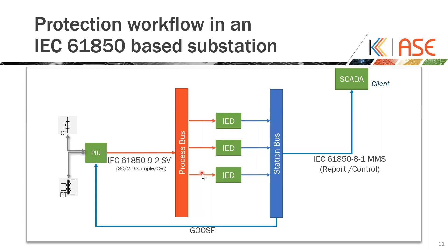As you all know, IEC 61850 provides an interoperable framework for substation protection, control, and monitoring. It's a protocol that defines the data exchange, also provides specific profiles and services, and a structured naming convention for the device data. So even if you have IEDs provided by multiple vendors, since we follow a common data model, the devices will talk in a common language, and the data will be represented in a common format, which aids interoperability. On top of that, IEC 61850 defines a standard configuration language. That means a common tool can create the configuration for multiple devices, even if they're coming from multiple different vendors. Still, all these devices will be able to understand a common configuration.